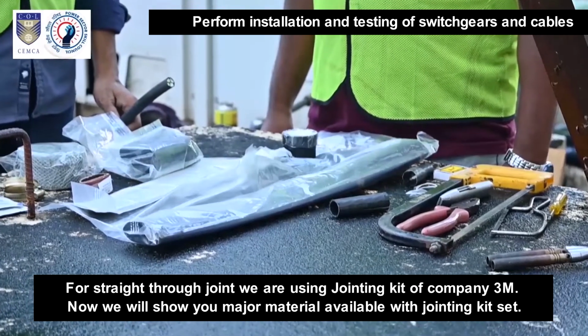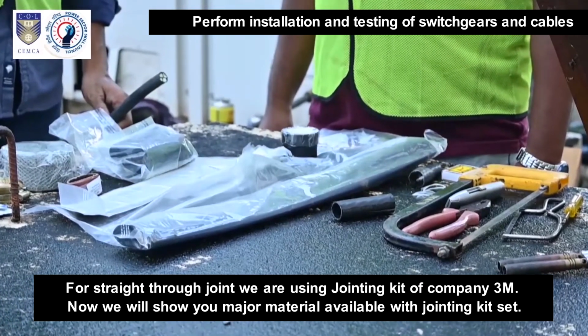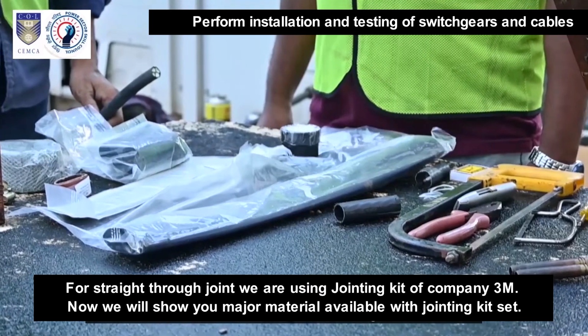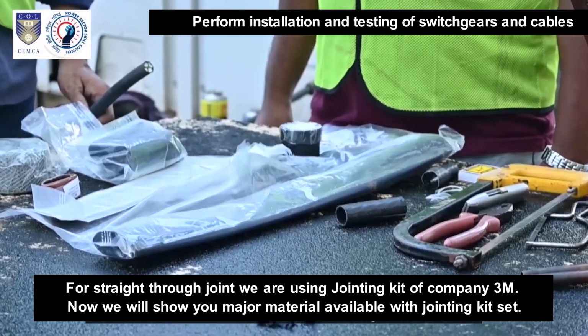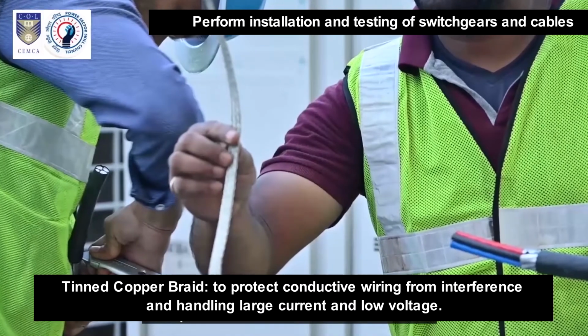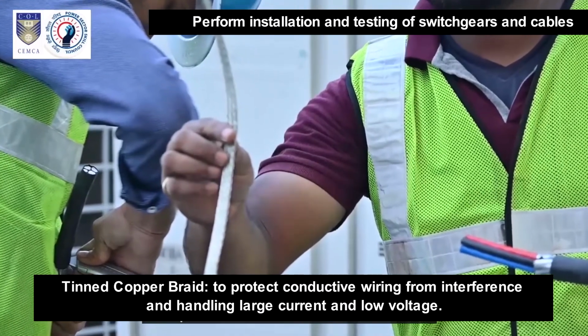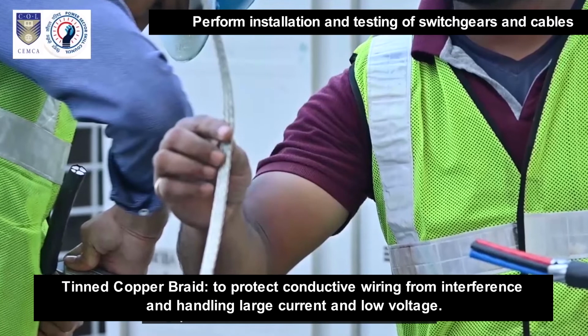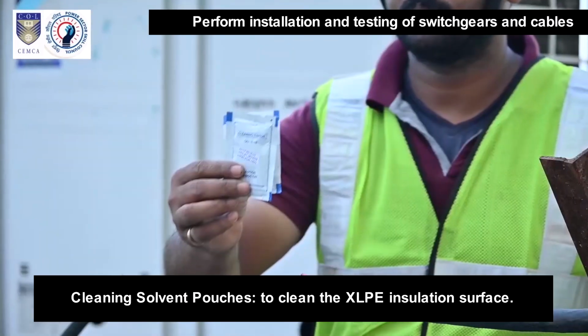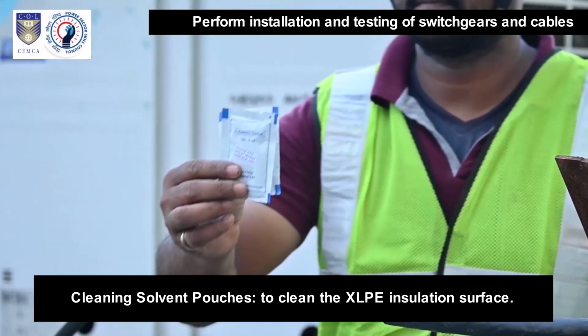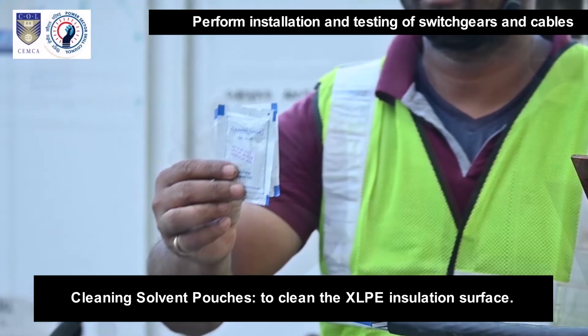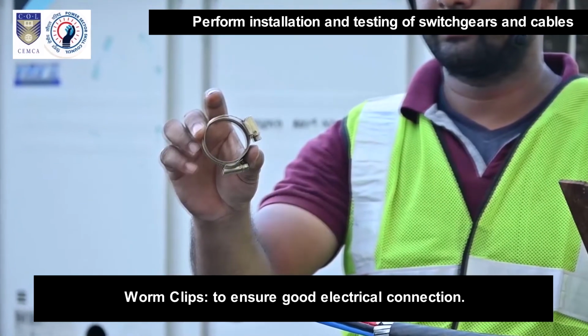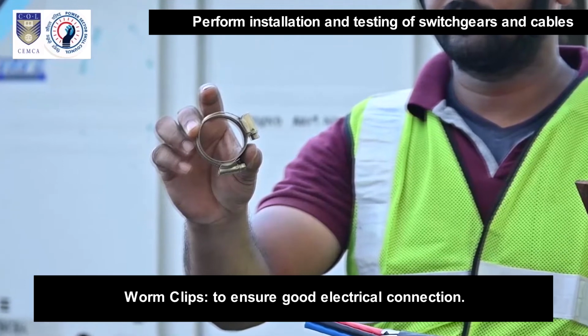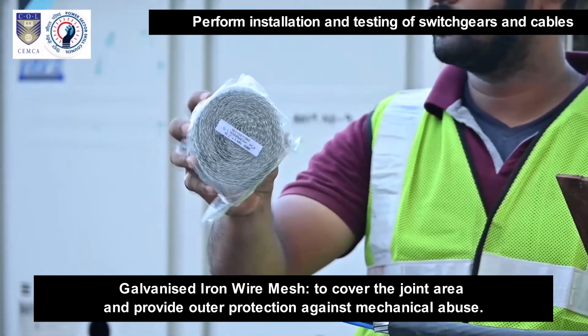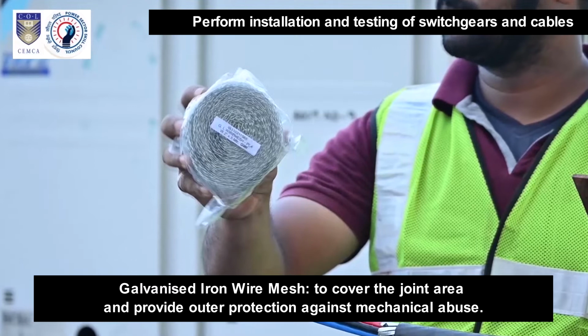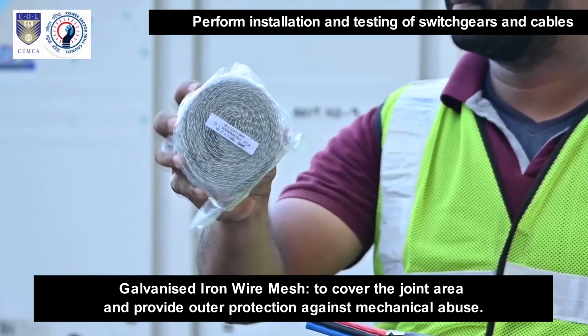For the straight through joint, we are using a jointing kit of company 3M. Now we will show you the major materials available with the jointing kit set. Tinned Copper Braid to protect conductive wiring from interference and handling large current and low voltage. Cleaning solvent pouches to clean the XLPE insulation surface. Worm clips to ensure good electrical connection. Galvanized iron wire mesh to cover the joint area and provide outer protection against mechanical abuse.